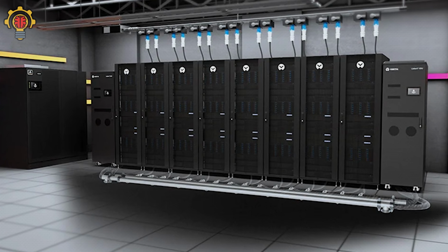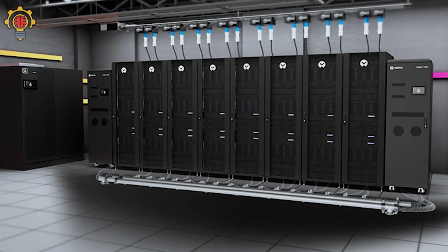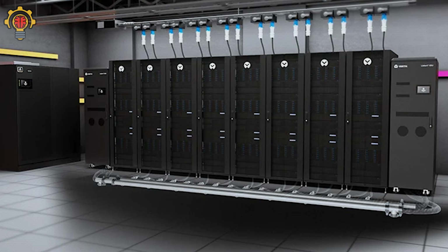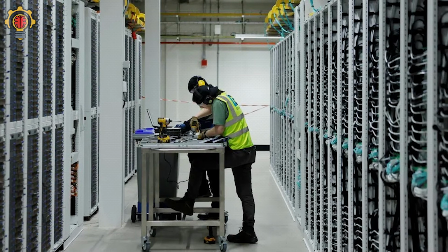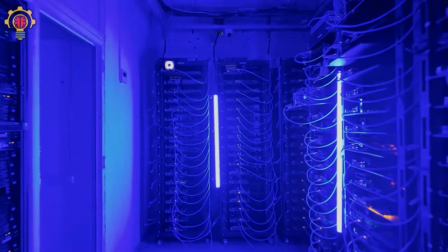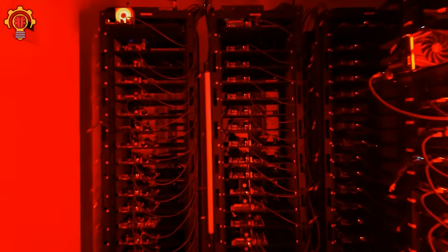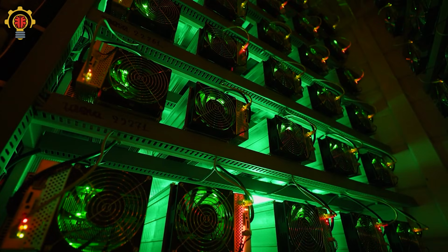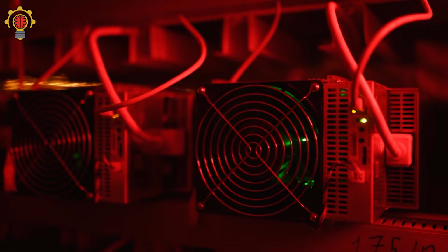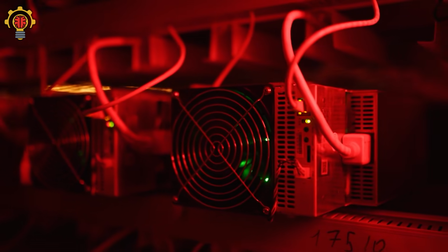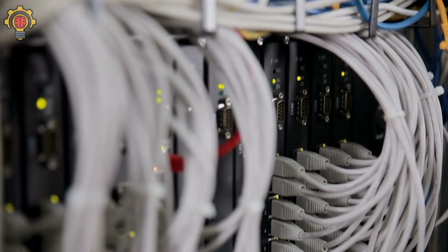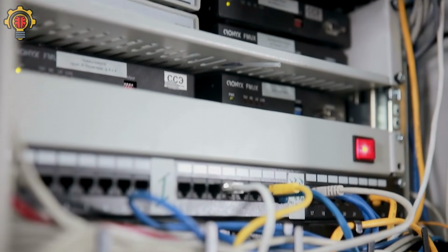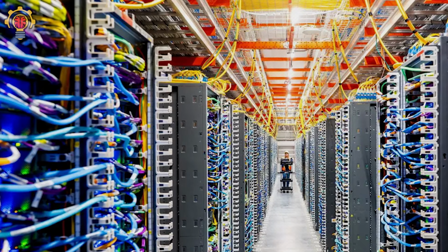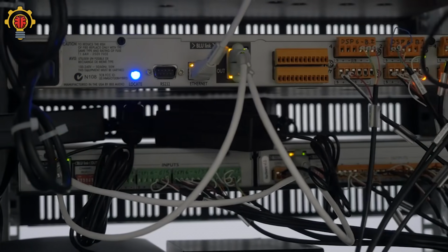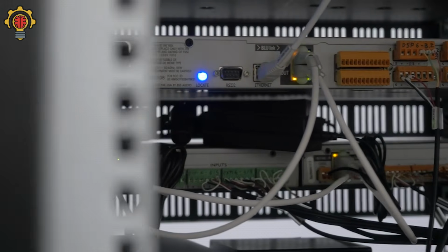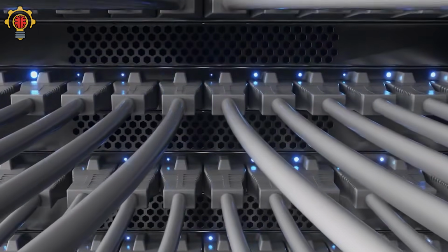But behind these liquid cooling systems, there's another critical component: the CDU, or Cooling Distribution Unit. The CDU acts like the control center for liquid cooling infrastructure. It separates the sensitive liquids circulating inside the server racks from the outdoor cooling systems like cooling towers or dry coolers. Inside the CDU, heat exchangers and pumps continuously move heat away from the servers while keeping the systems isolated for safety and reliability. One of the biggest advantages of these systems is efficiency. Many facilities can reduce their dependence on traditional refrigeration equipment, lowering electricity usage dramatically.